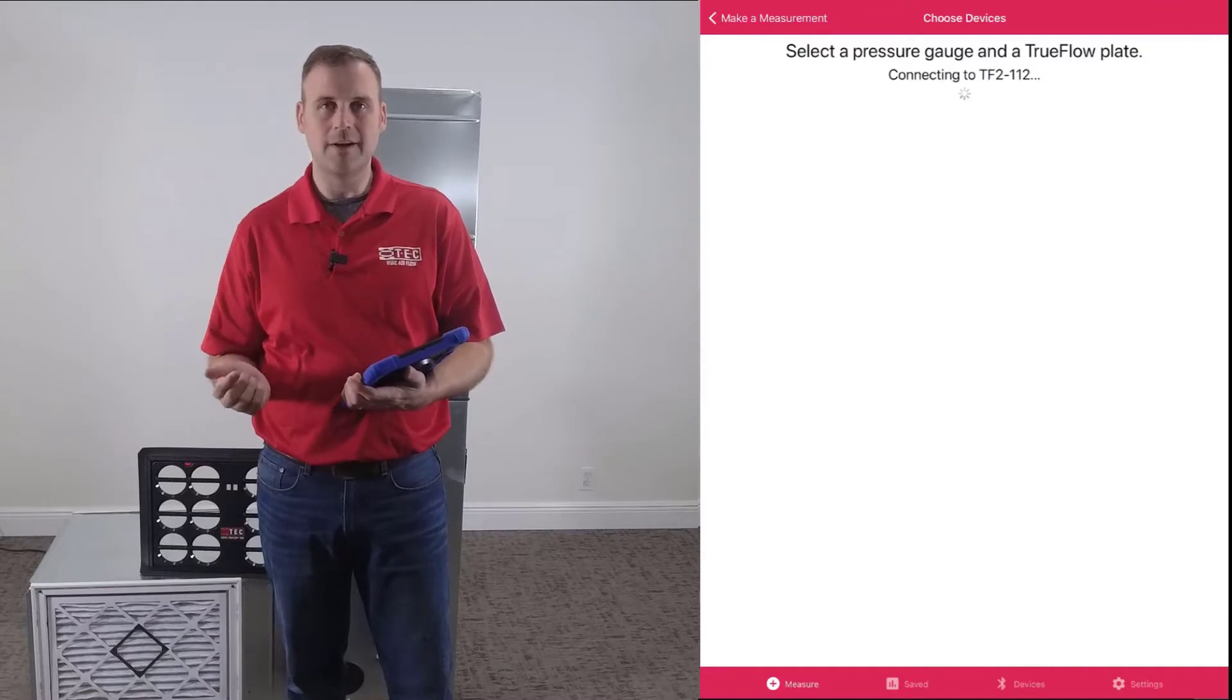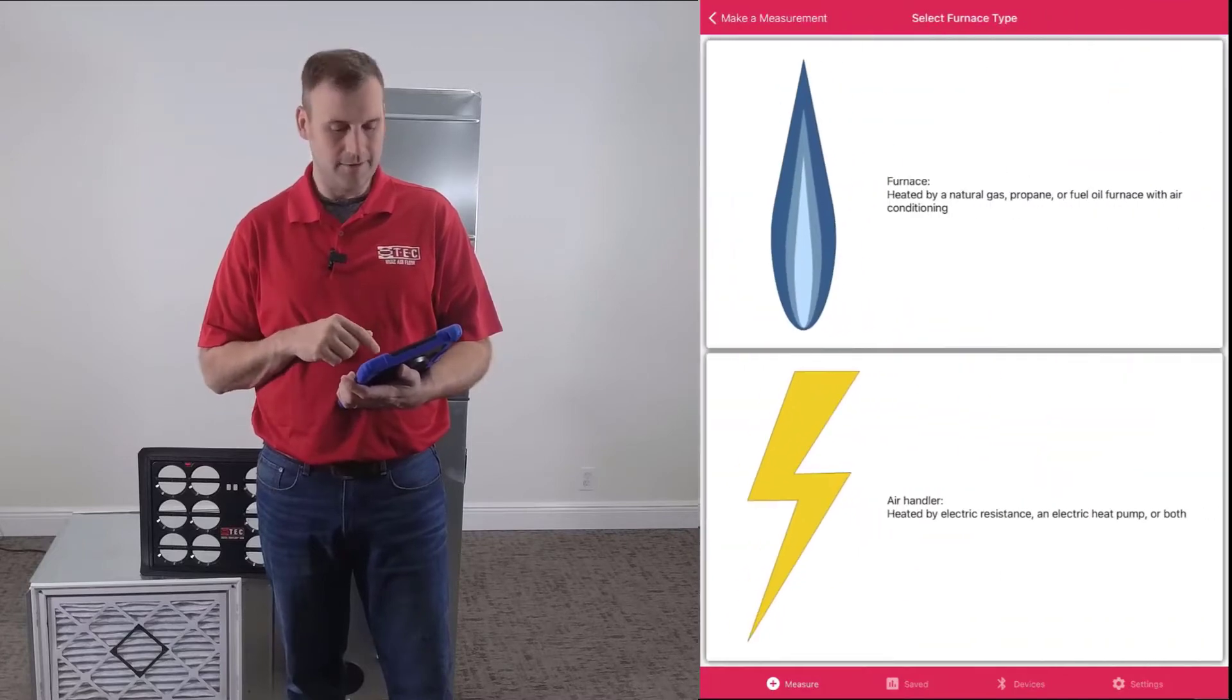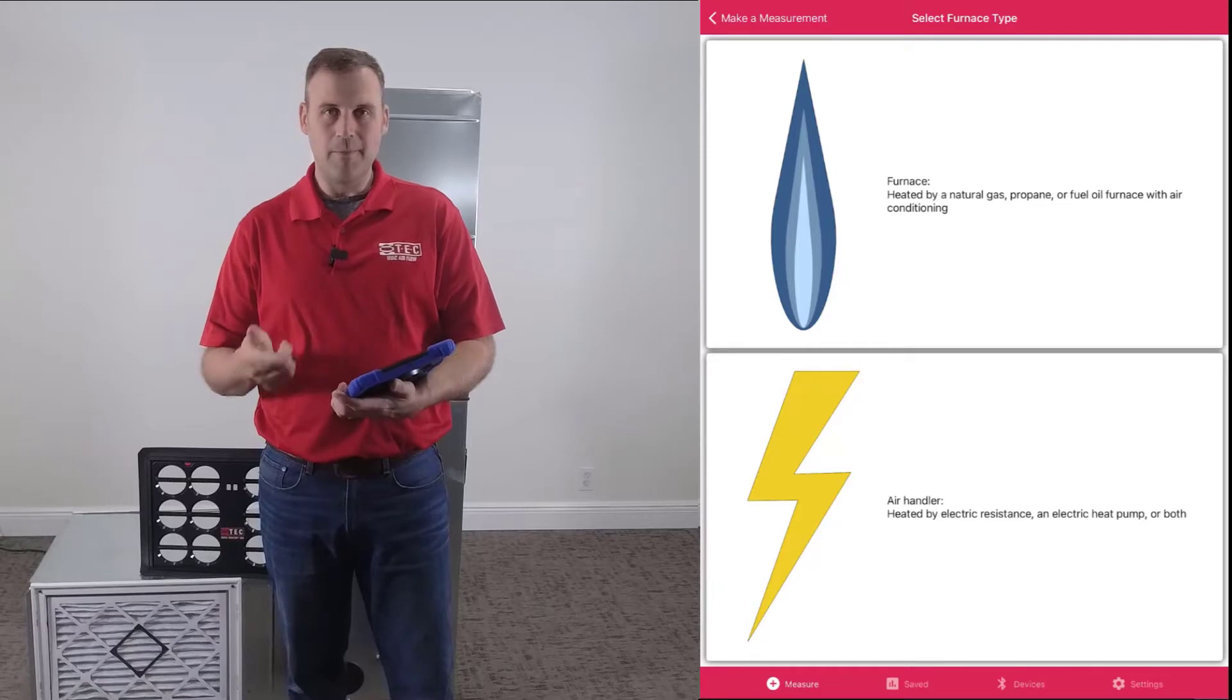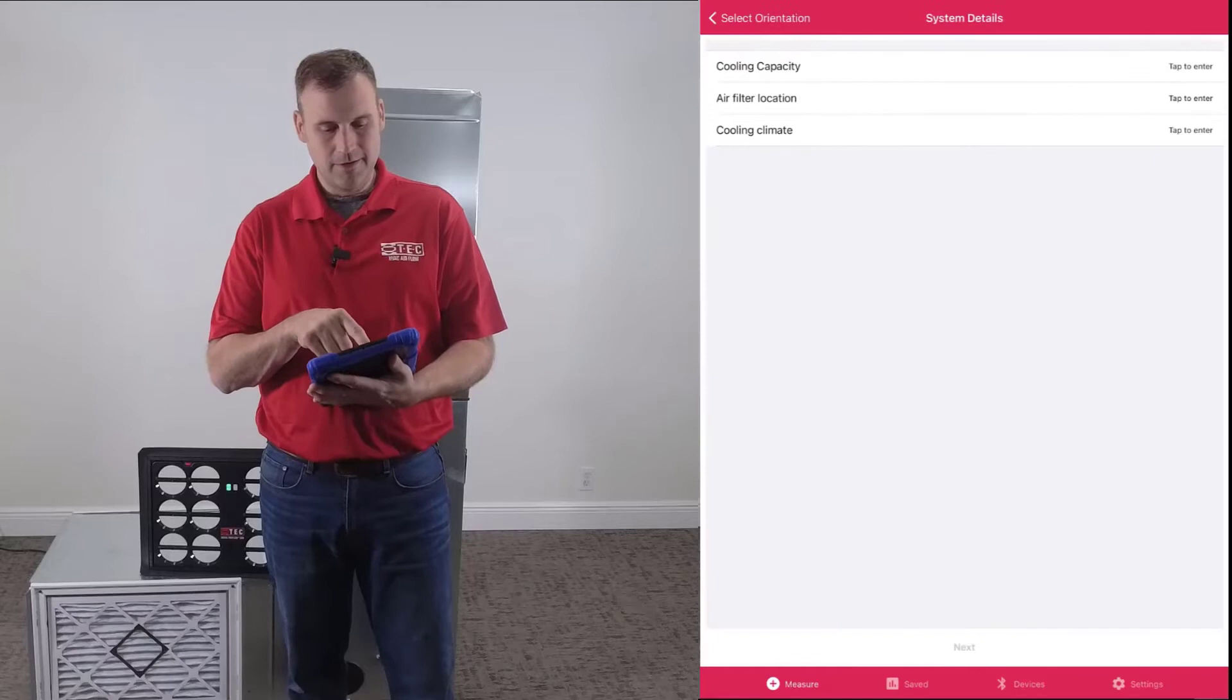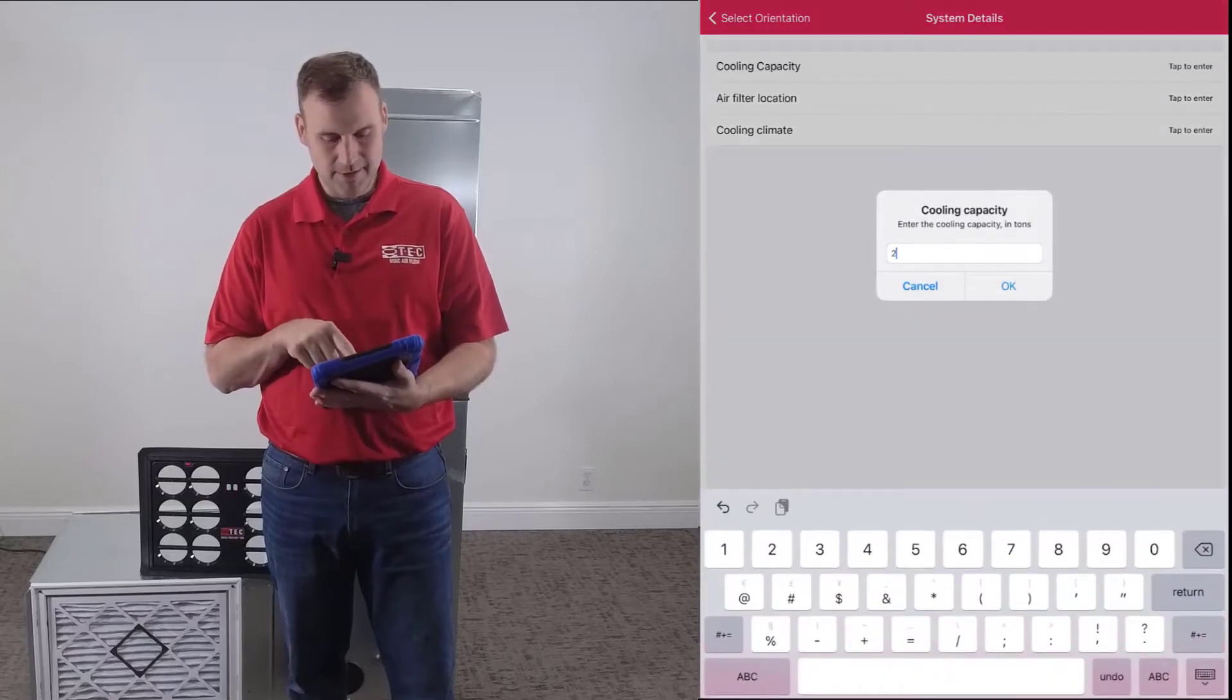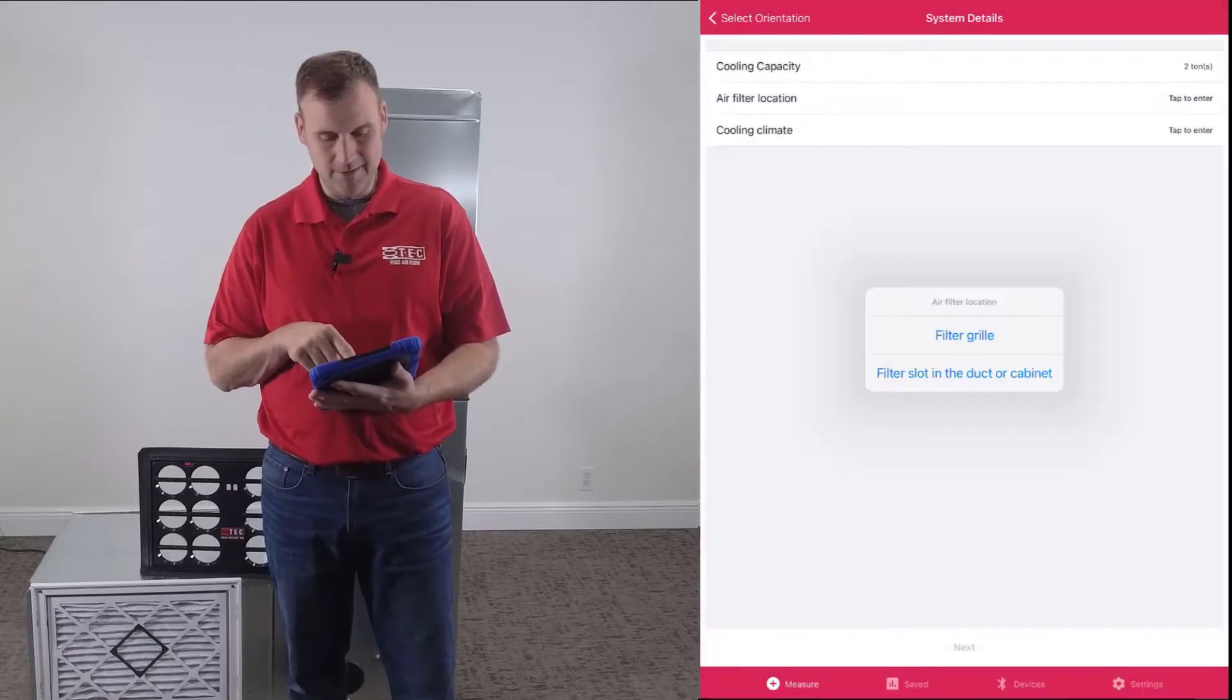Our app prompts us to the next step. We have an air handler, upflow, cooling capacity is a two-ton unit, air filter location is in the filter grill, cooling climate is 350 CFM per ton. Click next.